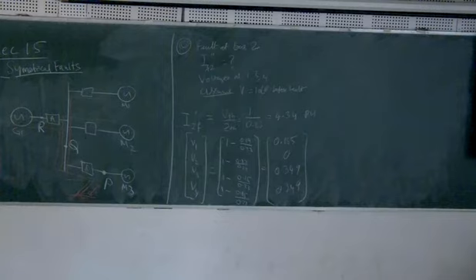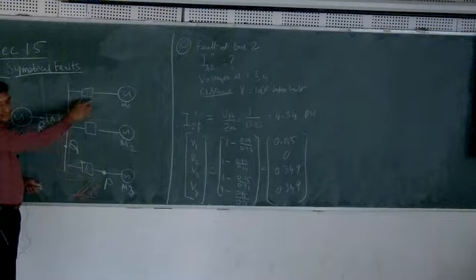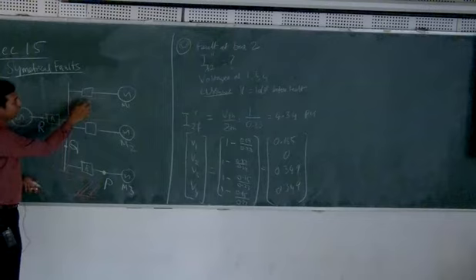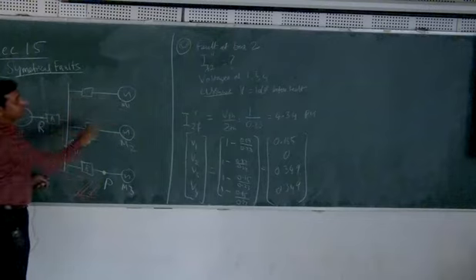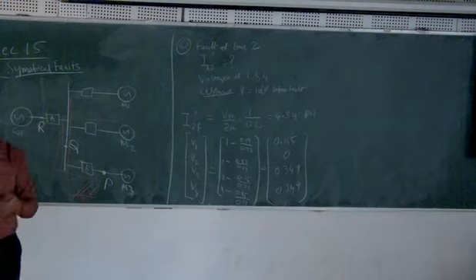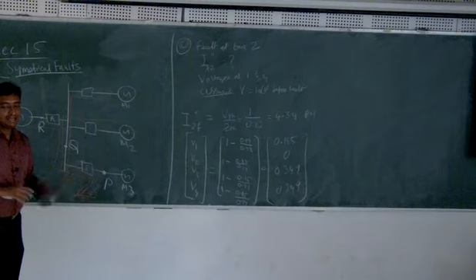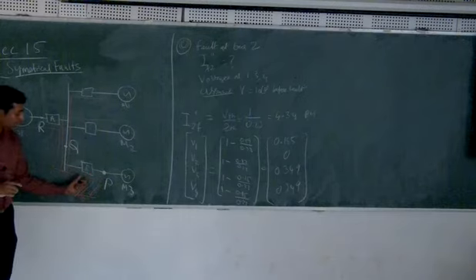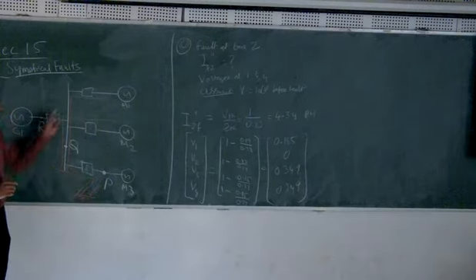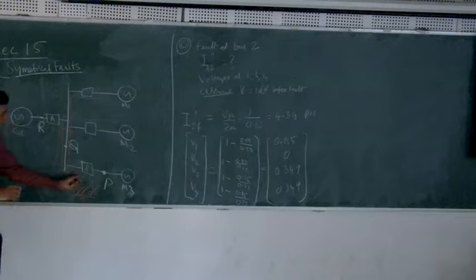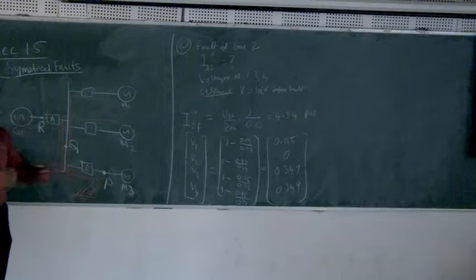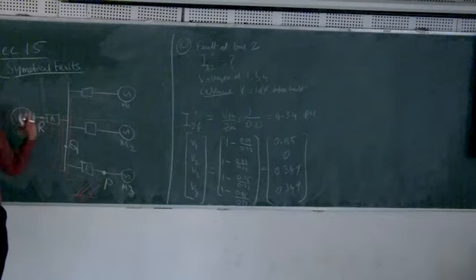But what happens if you open this circuit breaker? The machine G1 will not receive any power. The problem is not here, the problem is here. So ideally, only B should operate, and the other three should remain closed. If B operates, the fault is separated, the fault current suddenly becomes zero, and the normal current keeps going, and there is no interruption.